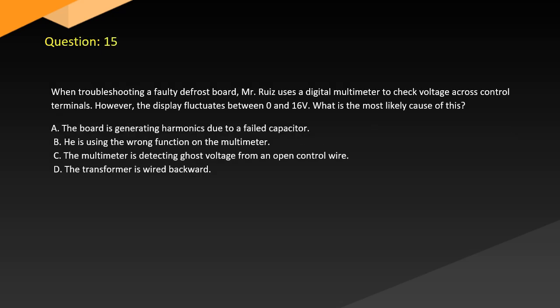Question 15. When troubleshooting a faulty defrost board, a technician uses a digital multimeter to check voltage across control terminals. However, the display fluctuates between 0 and 16. What is the most likely cause of this? A. The board is generating harmonics due to a failed capacitor. B. He is using the wrong function on the multimeter. C. The multimeter is detecting ghost voltage from an open control wire. D. The transformer is wired backward.